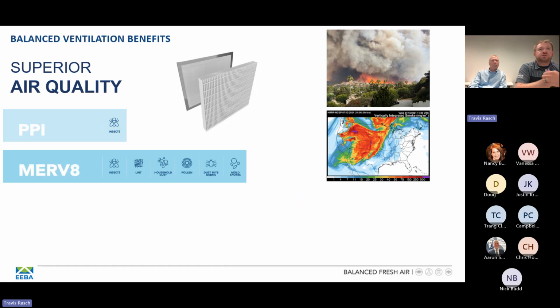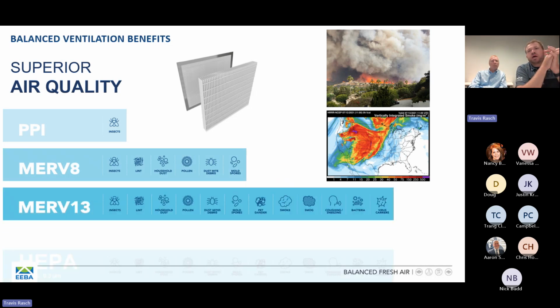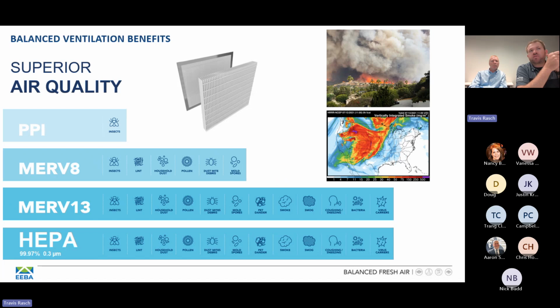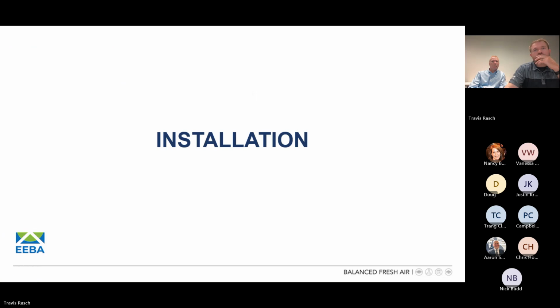Pat showed some of those images. We'll reuse those again. I talked about that at the very beginning as it relates to the key components of an HRV or ERV, and that first one being the filter. As you may be aware, there's a multitude of levels of filtration. What you're going to find in the industry, and we've certainly moved closer and closer, is MERV 8 becoming the standard as it relates to filtration. You can see the different particulate matter that these levels of filtration capture. And as you work your way towards MERV 13, ultimately HEPA, you'll see how capture efficiency only increases, as well as our ability to capture the smaller particulate matter that Pat had mentioned earlier in the discussion.